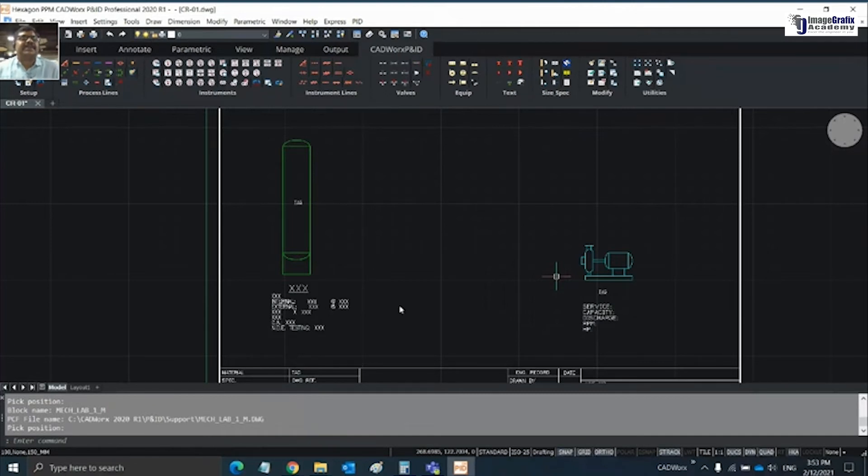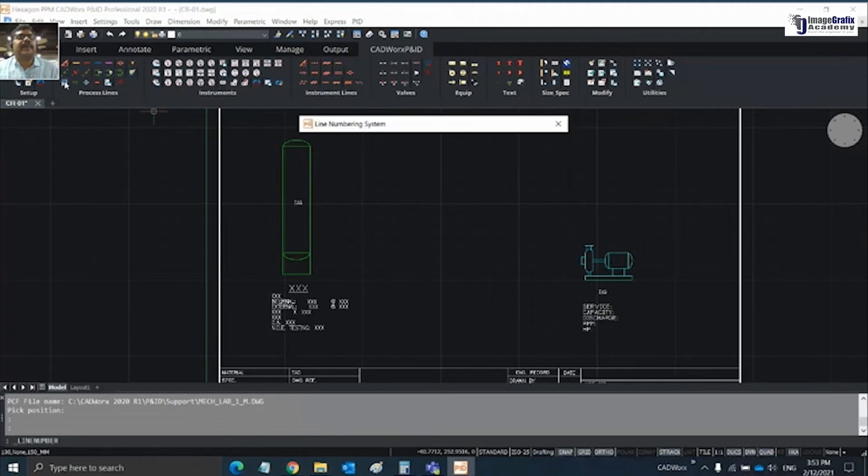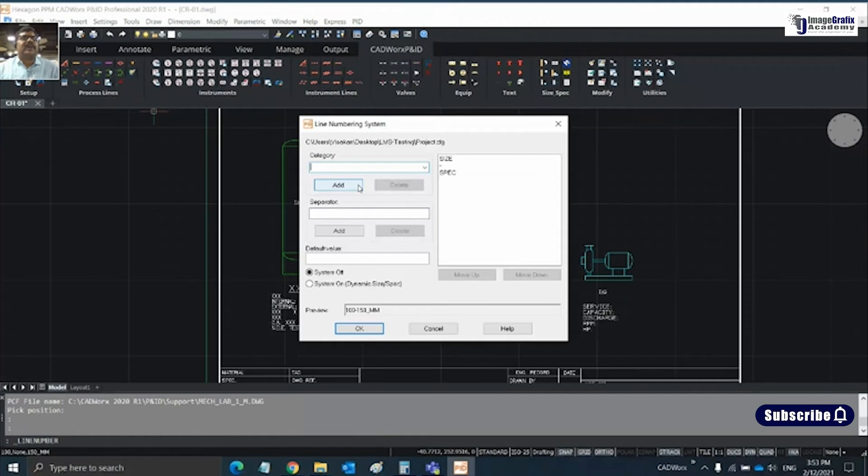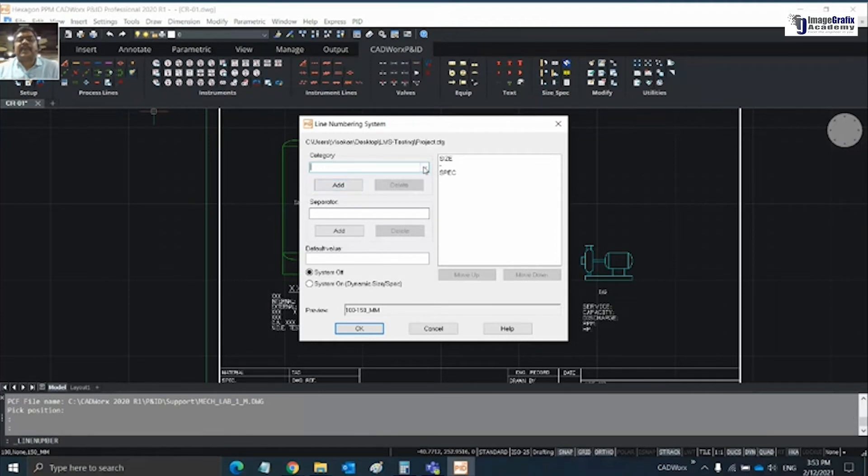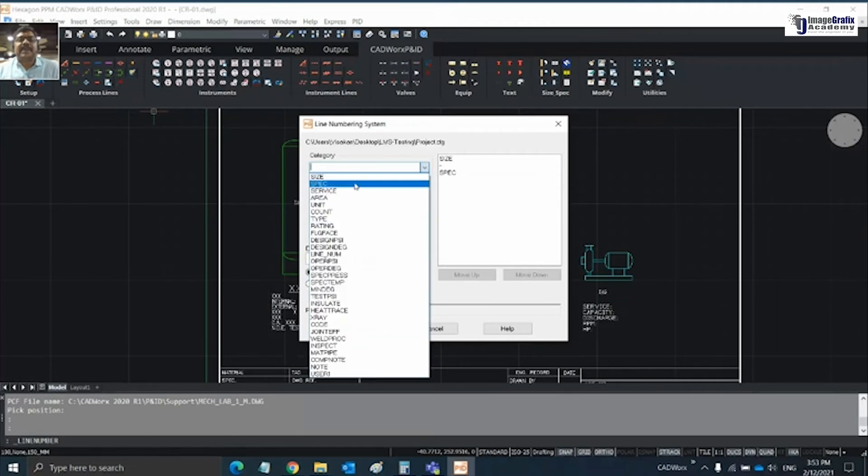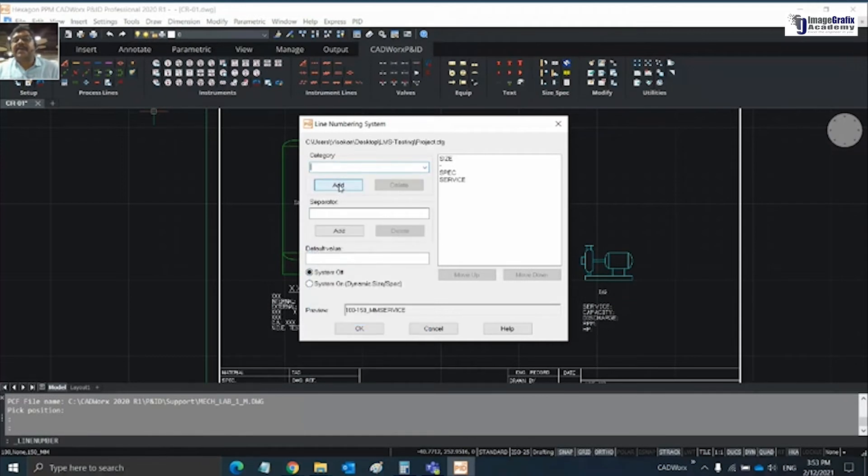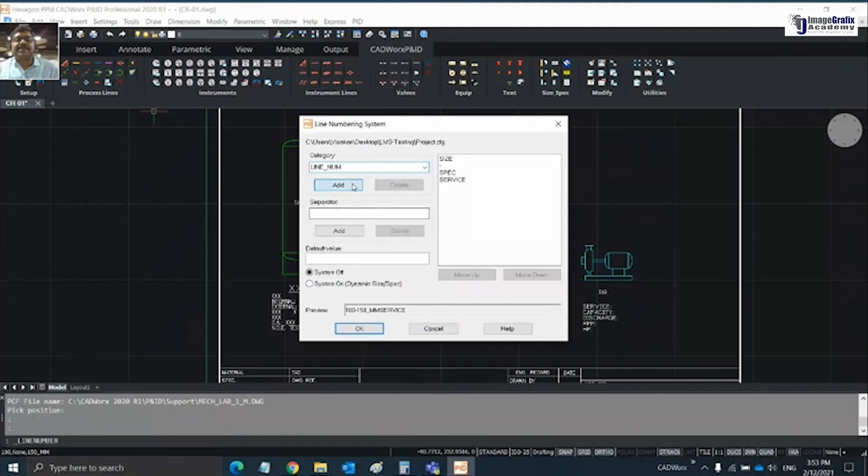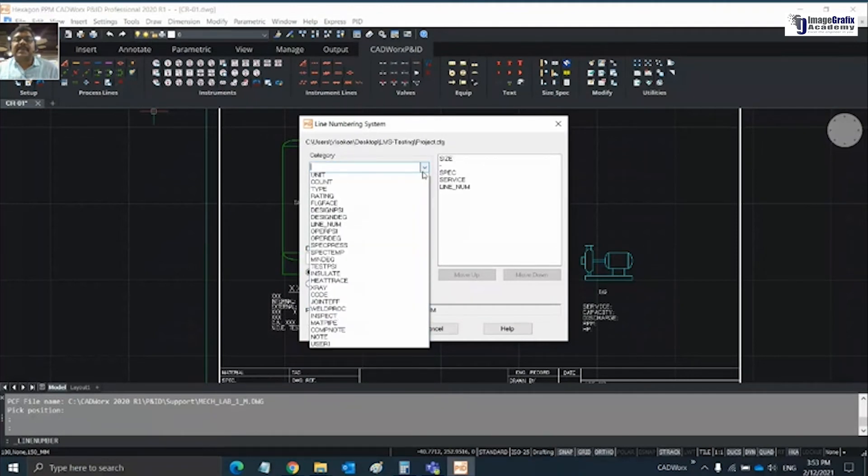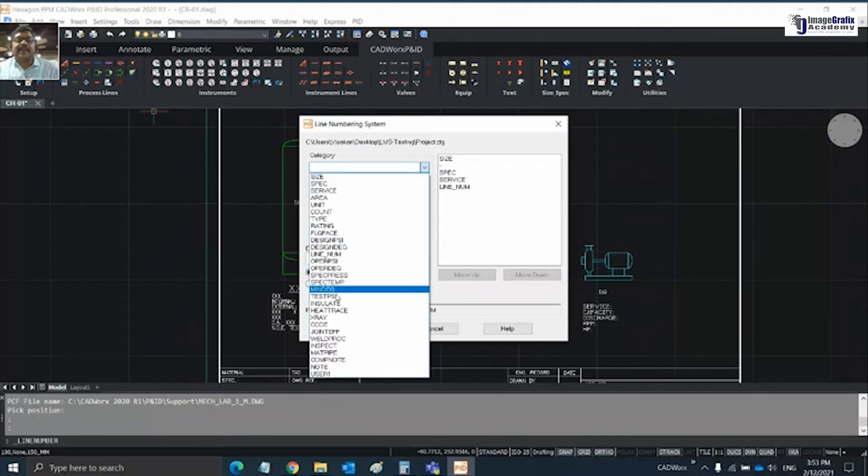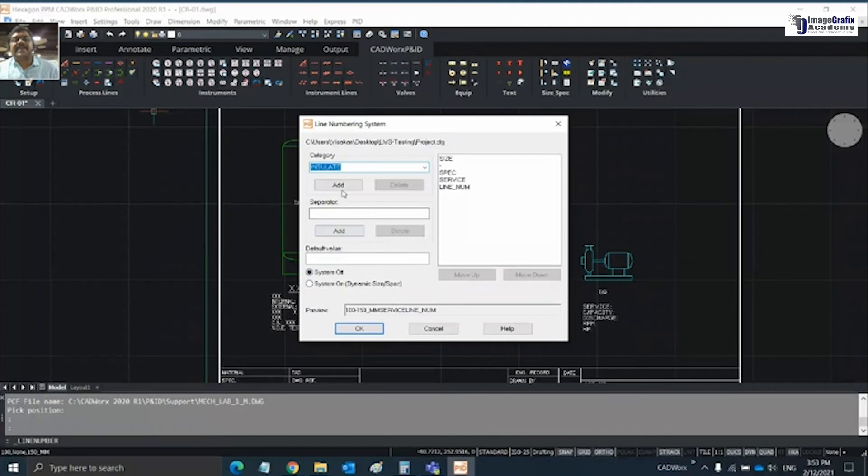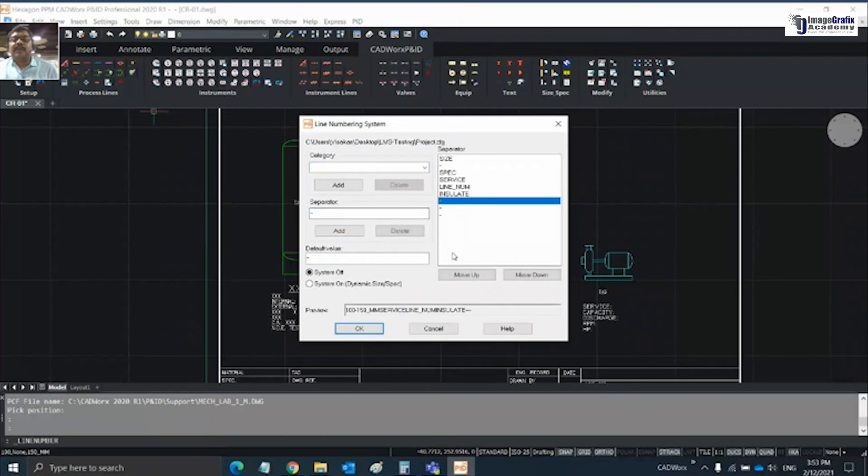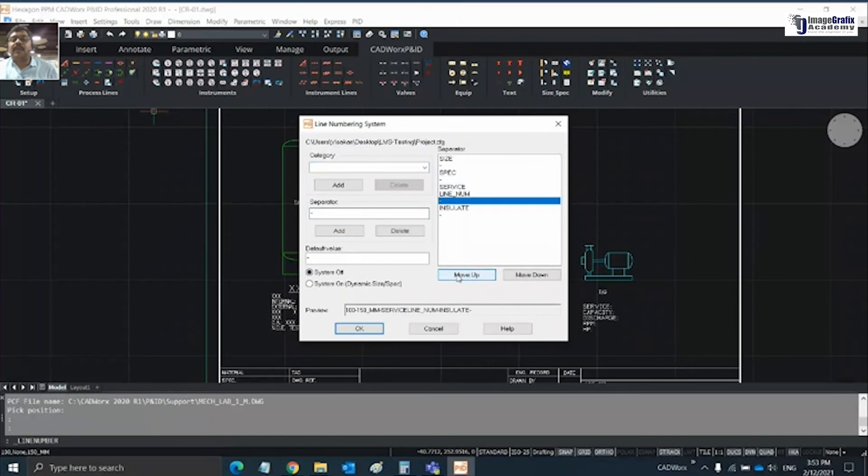Once this is done, my next thing is to create a process line connecting this vessel and the pump. To start with your process line, we're going to define the tag format - what tag you want to use or what the project standard is. Let me choose service as the next input I need, then line number, and insulation as the third one or whatever standard your customer asks for.